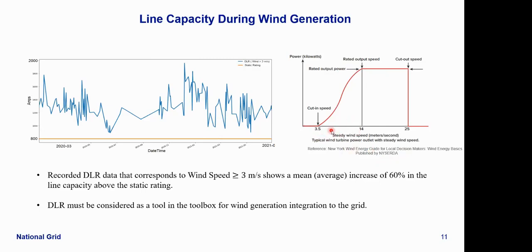For a general wind turbine, of course there's design-specific variation, but in general, the cut-in speed is the speed at which wind turbines start to function. You'll see the blades spinning until they reach their rated full power. The cut-in speed is 3.5 meters per second, and at 14 you're at the rated power. Again, these numbers can vary slightly based on the design. So if I only look at my DLR data for wind speeds of 3.5 meters per second and above, this is the DLR that I'm getting.